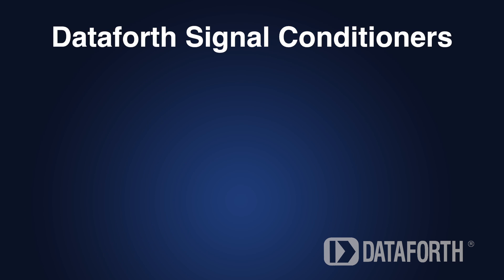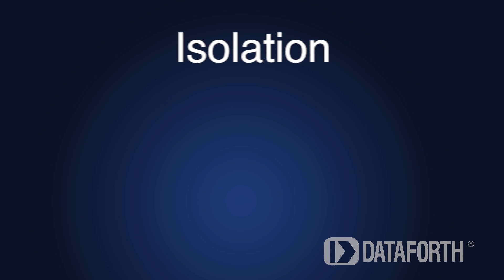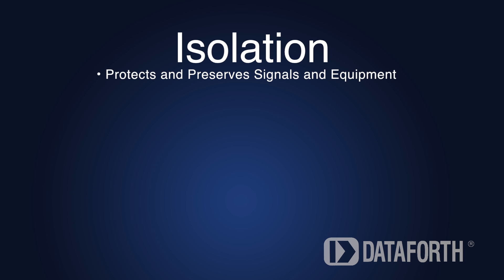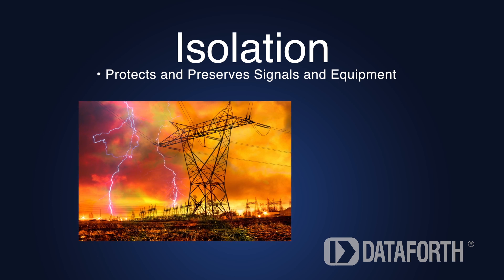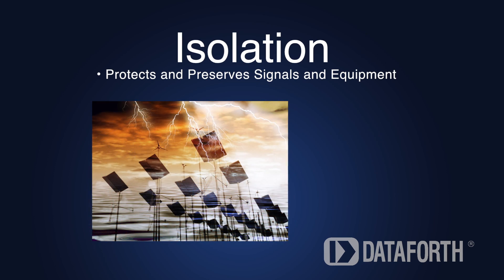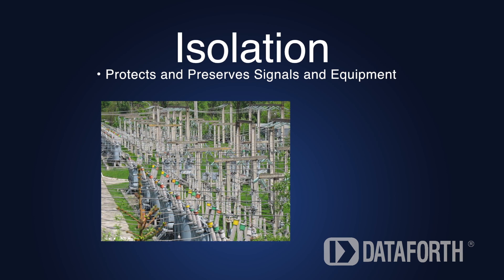Signal conditioners ensure the accuracy and reliability of the signals from sensors. To do this, they must meet three criteria. The first criterion is isolation. Isolation is critical because it protects and preserves signals and measuring equipment from the effects of hazards like electrical noise, transient power surges, and hidden ground loops.